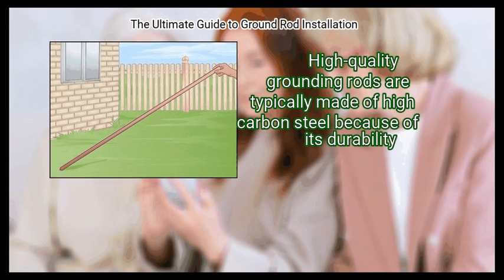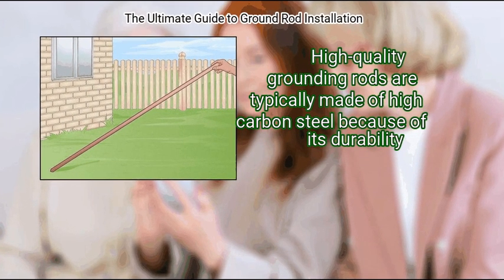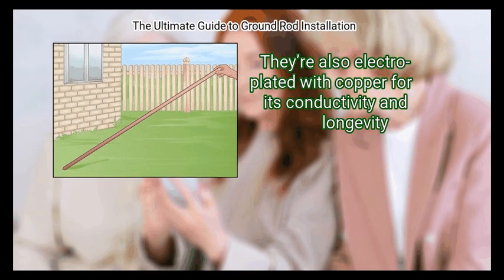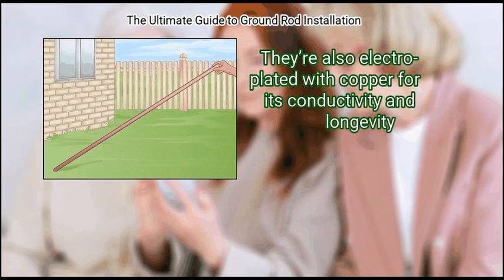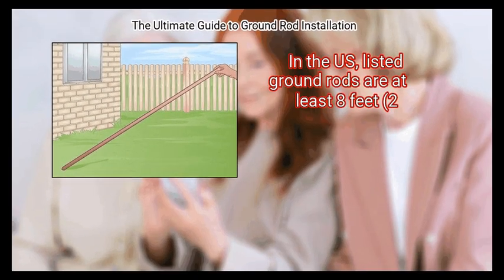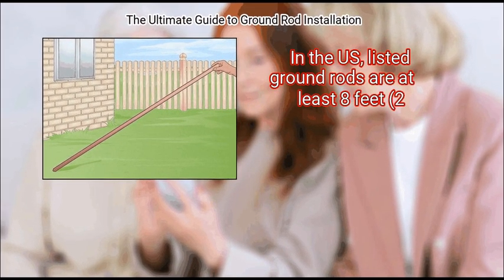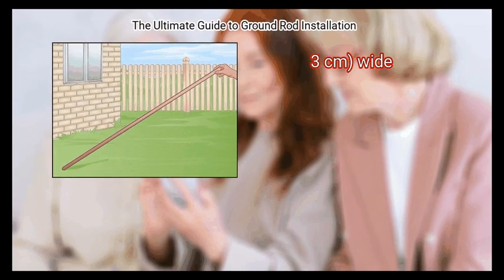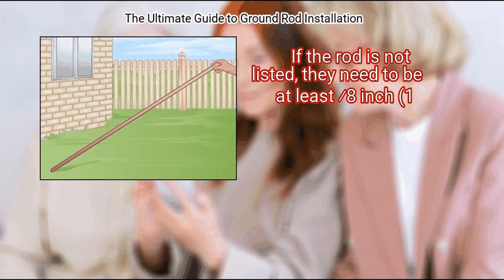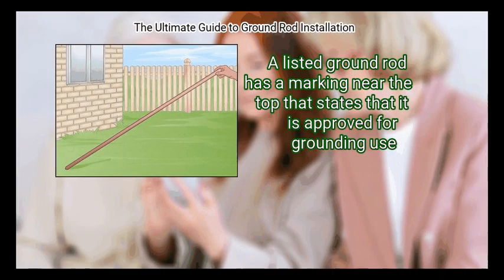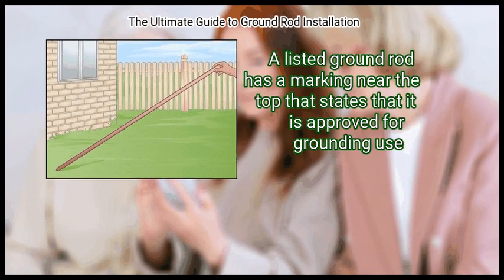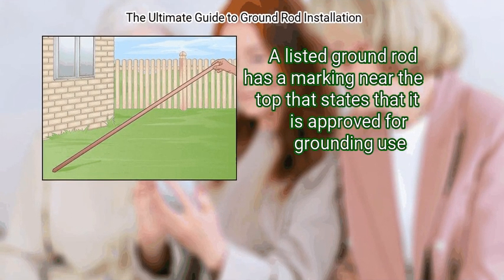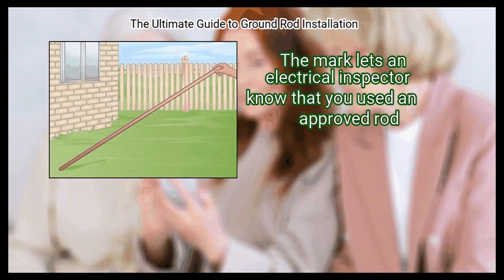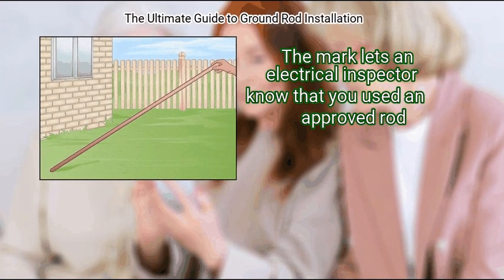High quality grounding rods are typically made of high carbon steel because of its durability. They're also electroplated with copper for its conductivity and longevity. In the US, listed ground rods are at least 8 feet, 2.4 meters long and 5/8 inch, 1.6 centimeters wide. If the rod is not listed, it needs to be at least 1/2 inch, 1.3 centimeters wide. A listed ground rod has a marking near the top that states that it is approved for grounding use. The mark lets an electrical inspector know that you used an approved rod.